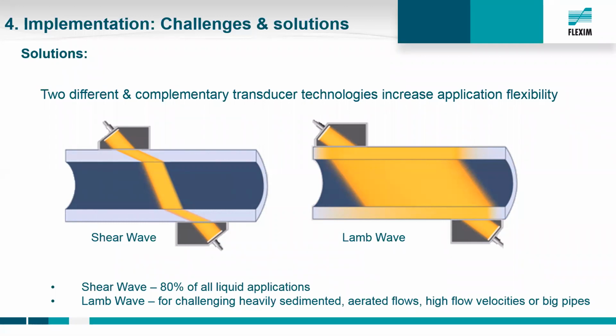So there are two common techniques to send the ultrasonic signal through the pipe and media. The one is lamb wave and the other shear wave. So shear wave, displayed on the left side, the technology is the most popular on the clamp-on market. The shear wave transducers operate with transversal waves. So such ultrasonic waves are transmitted by the transducer into the pipe wall. The waves are reflected in the pipe wall and transmitted as well into the water.